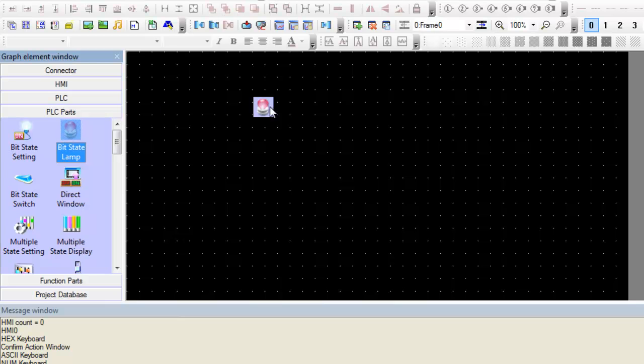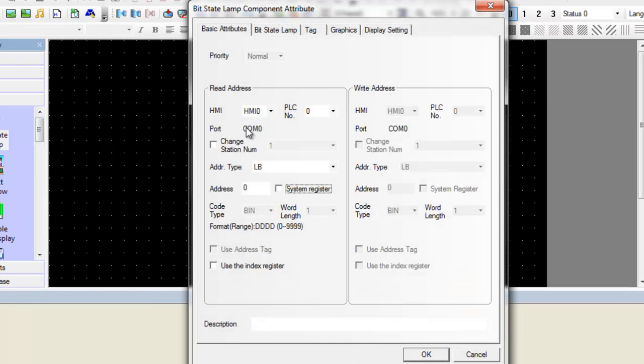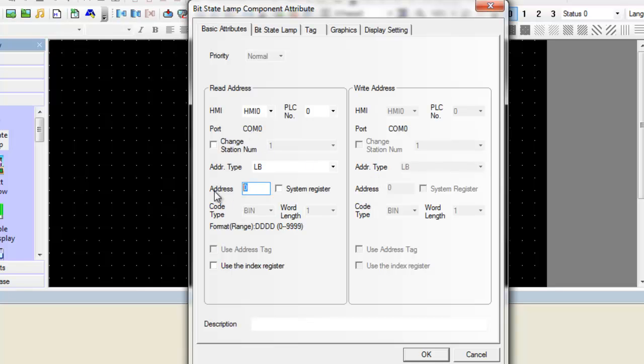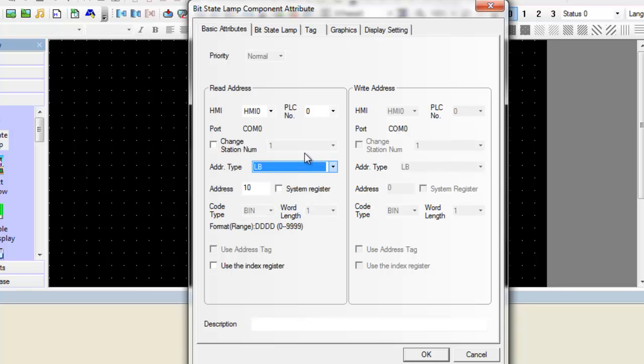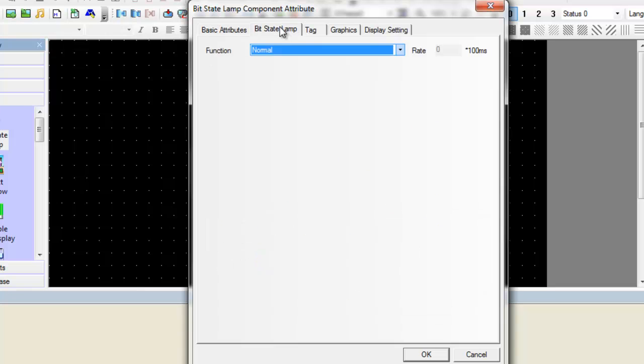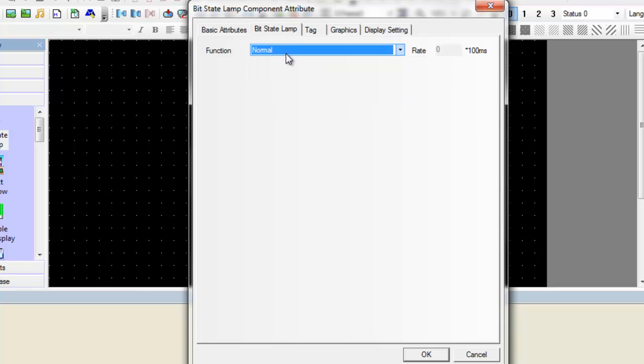Click the bit state lamp icon and drag it over to the configuration window. We must now input the bit address of the PLC register that will control our lamp state. The address type depends on the controller or PLC you are using. For today's purpose, we will be using LB, local bit. We will just select the normal function which displays the state of the PLC register.